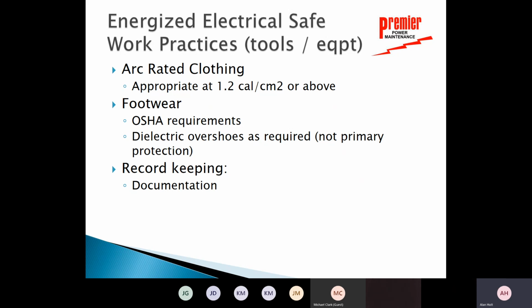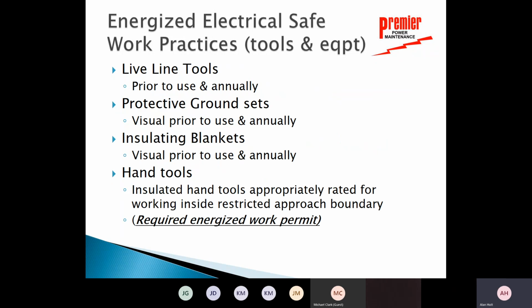Their footwear requirements. We have boots that we have to do, and we have to do record keeping documentation that we have been trained and we utilize this equipment, and documentation of the testing of the various pieces of equipment. If we talk about live line tools, hot sticks, prior to every use, visual inspection, annual sticker on it that's been electrically tested. We do that. Protective ground sets, visual prior to use, and annual testing. We do that on an annual basis.